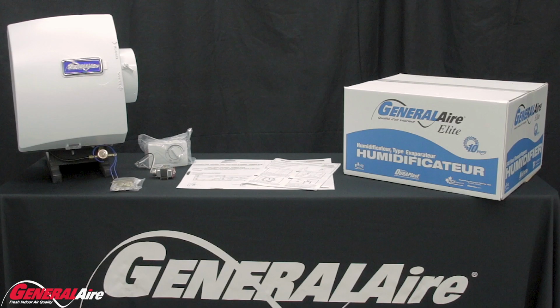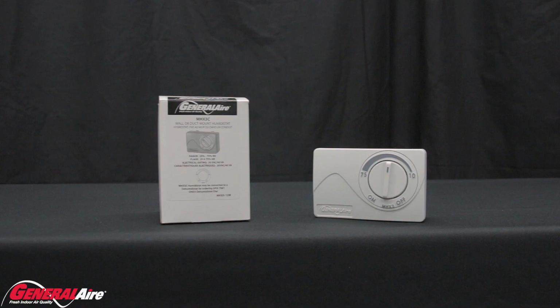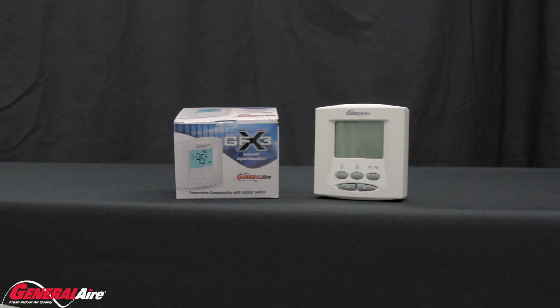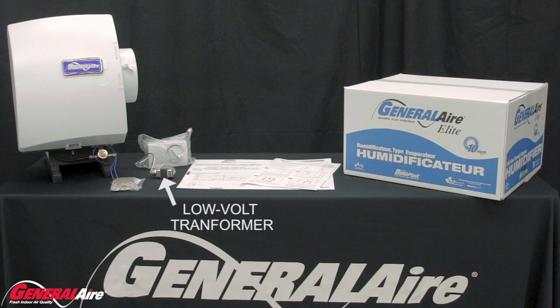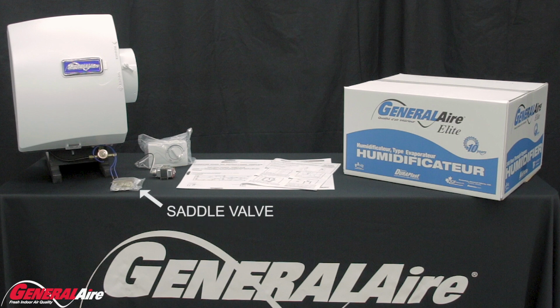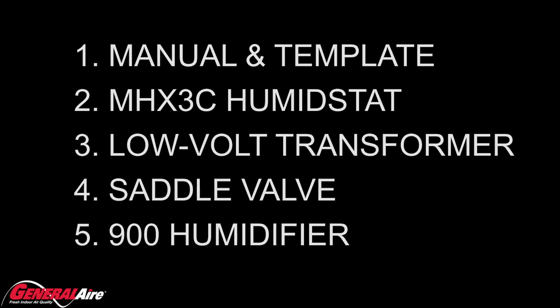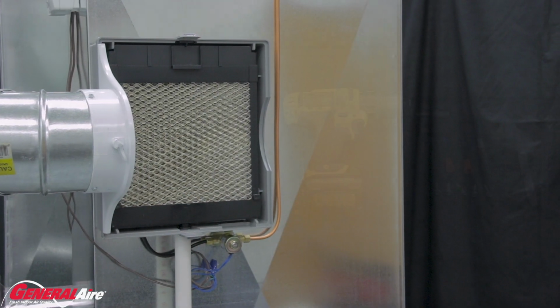First, locate and identify the following items in the box: installation manual and duct cutout template for the humidifier, MHX3C manual Humidistat, and if you are installing a 900A, the GFX3 automatic Humidistat, a low-volt transformer, 120 volts to 24 volts, a self-piercing saddle valve waterline adapter, the 900 humidifier. You'll also find your vapor pad inside the humidifier, assembled and ready to go.